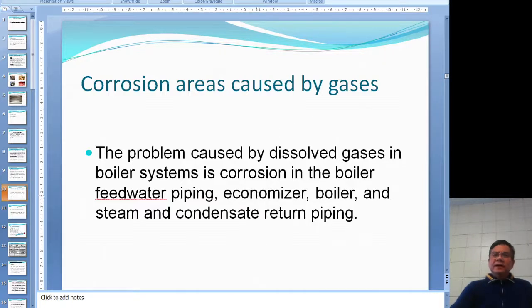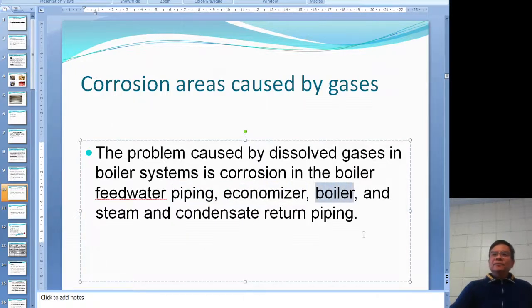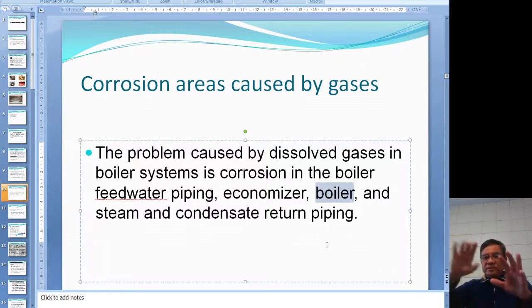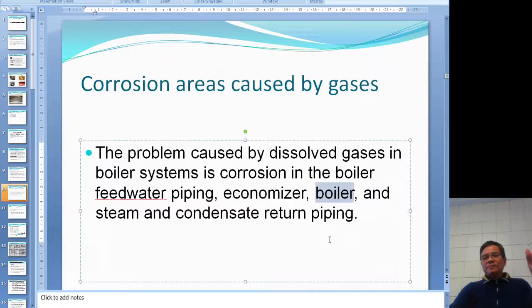Corrosion caused by dissolved gases affects different areas of the system. The feed water pipe and economizer are one category, where the temperature is not yet very high. Inside the boiler is another area. After steam leaves the boiler, the steam pipe must be considered. And when the steam condenses, the condensate return pipe is yet another category requiring different treatment.